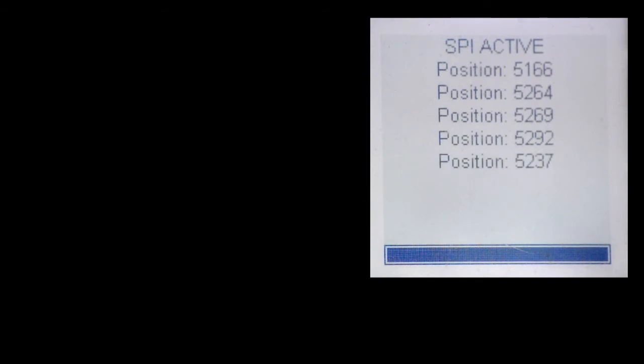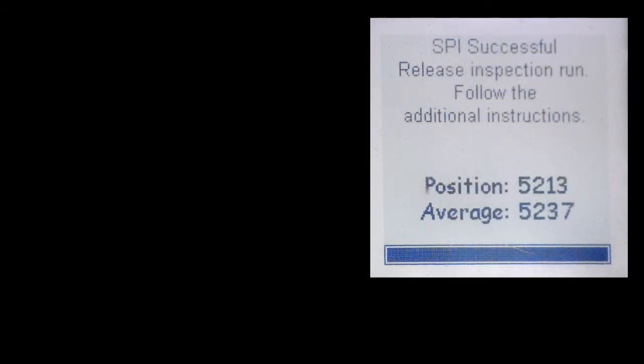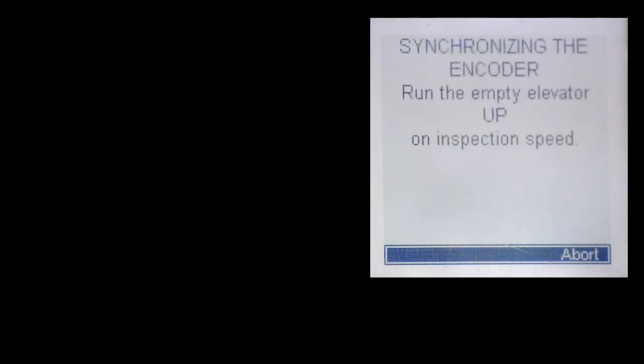Here you can see that the position samples are being taken, and they are different from the last learn. They're all consistent within a few hundred counts. When the process completes, you'll see the position and the average will be saved in the LE06 encoder pole position parameter.